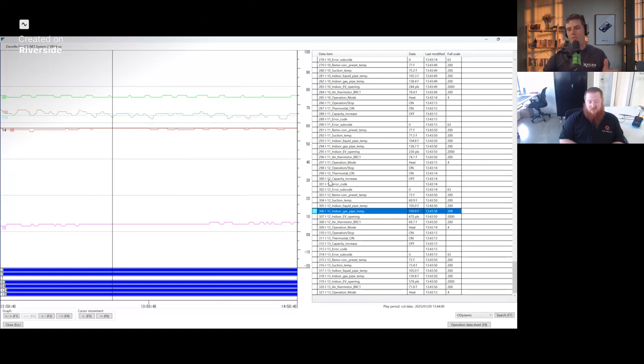There is a problem there. It means your refrigerant is moving really slow or the volume isn't there. And the same with subcooling. If the subcooling liquid temp coming out of your indoor unit is 103 degrees, but it turns to 46 degrees by the time it makes it to the outdoor unit, there is a huge problem. Large temperature differentials where there shouldn't be any, should be none, or limited, is a problem.